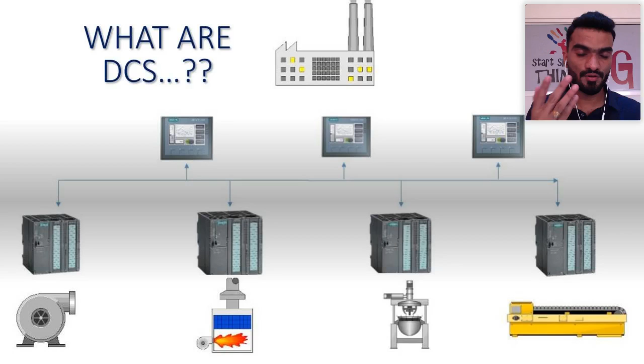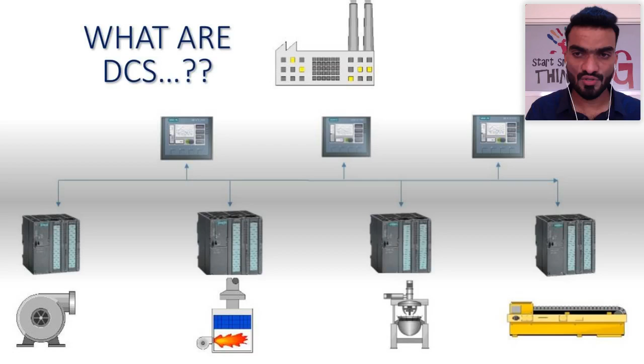For example, an area of motors and fans can be connected to a PLC, and this PLC is connected to DCS. So your furnace area, filling areas, conveyors, all this can be taken into the DCS, and the DCS at plant level controls and monitors everything, giving you a good reporting system in a faster manner. That's all about DCS. Its applications are mostly in pharma and power plants, for process automation, where one process interlocks with another. These are the areas where we install DCS systems to have a foolproof solution.